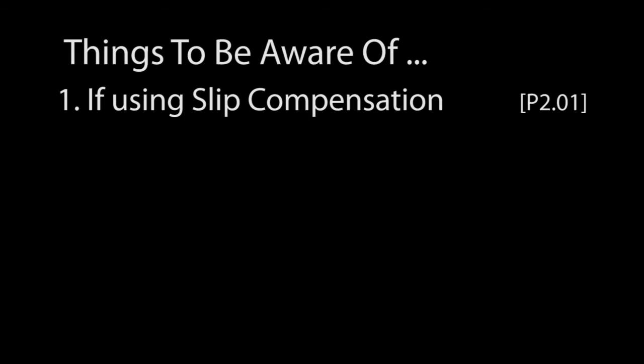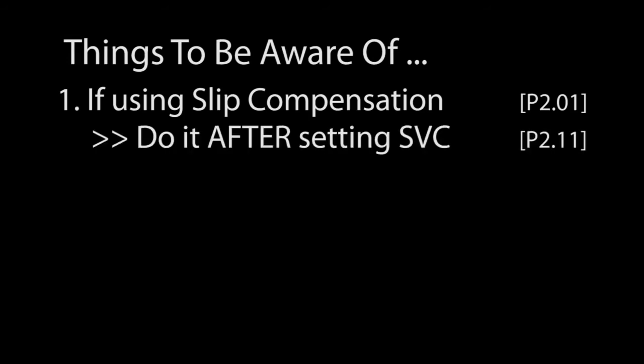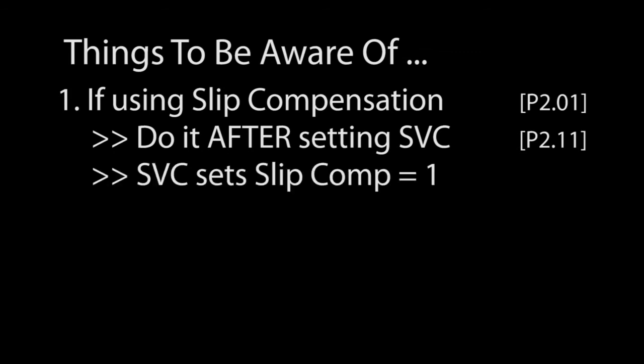There are a couple of things you need to be aware of. First, if you use slip compensation to tweak the performance of the drive, make sure you do it after setting the drive for sensorless vector mode. Each time you set the drive for sensorless vector, slip compensation gets set to 01, so be sure to update that after you switch the mode.